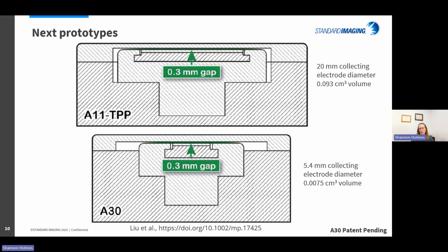And so it is something that can be corrected for, or you use them the same way you do microchambers, where you don't necessarily apply a P-ion, and you just use them in the configuration that they are calibrated for. So the exact recommendation on that will have to come from the research community, I think, more than from us, but we are trying to make it with as minimal a P-ion as possible. It is a little difficult in a parallel plate chamber with electron beams just because you generate constant currents. It's part of the nature of the beast.